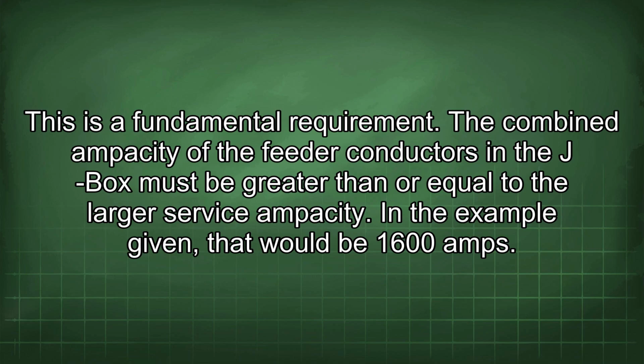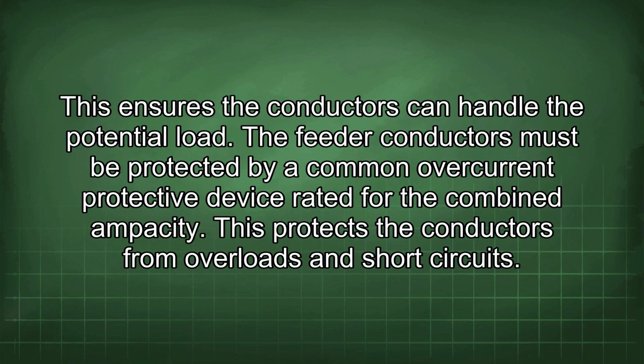The combined ampacity of the feeder conductors in the J-box must be greater than or equal to the largest service ampacity. In the example given, that would be 1600 amps. This ensures the conductors can handle the potential load. The feeder conductors must be protected by a common overcurrent protective device rated for the combined ampacity. This protects the conductors from overloads and short circuits.